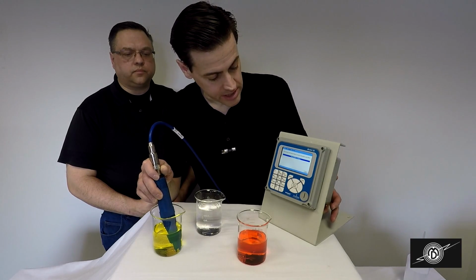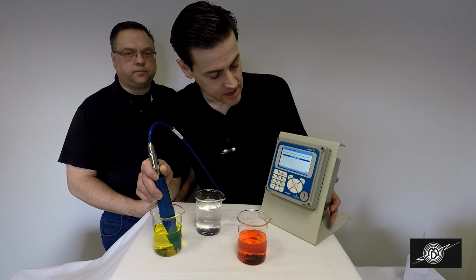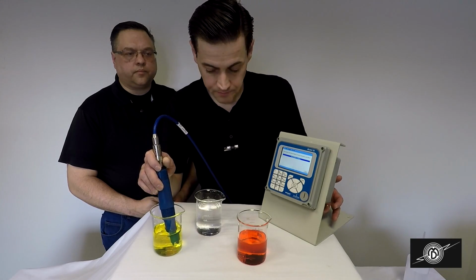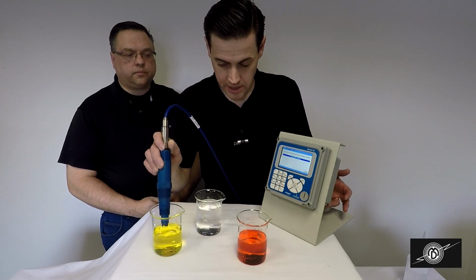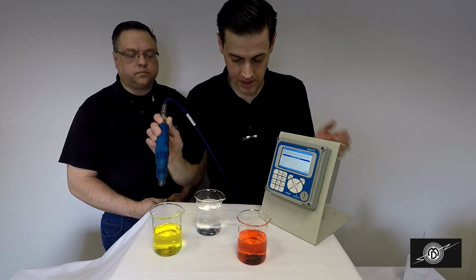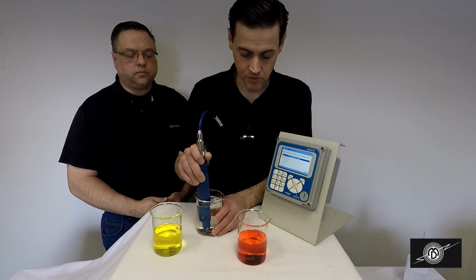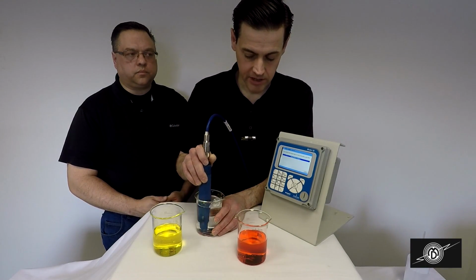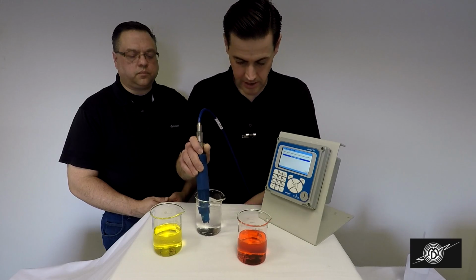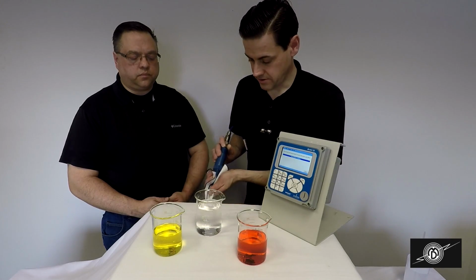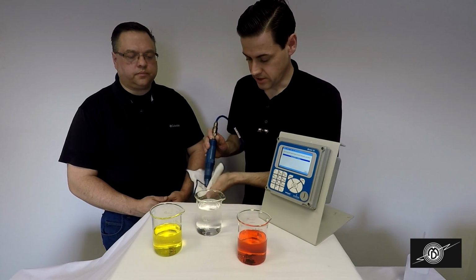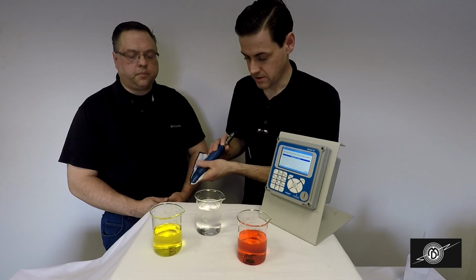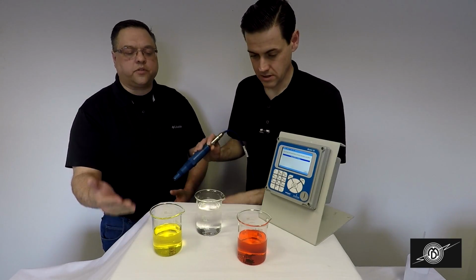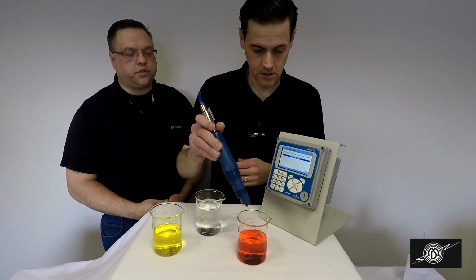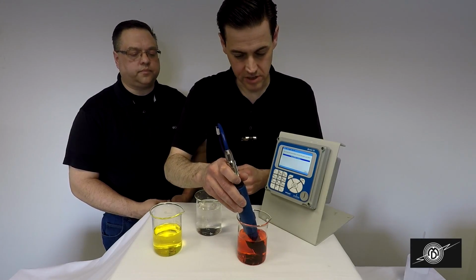So it says place the sensor in the 2nd buffer, and I notice that it skipped a part of the process. What we want to do in between is we do still want to clean off that sensor as we go into the next buffer. Okay, it takes just a few seconds. You don't want to contaminate one buffer solution with your other buffer solution. Okay. This buffer I'm using is a 4 buffer.